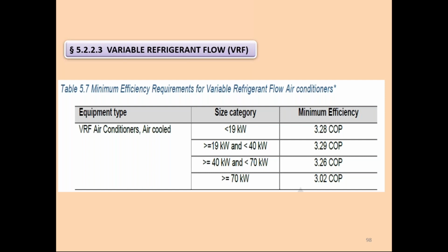And also part load performance of VRV is good. So that means for 10 tons of air conditioning, you will have to install probably 13 or 15 tons of air conditioning VRV system, so that the system will operate at part load and will be efficient. So your first cost of VRV is also very high because you use more gas, you use copper, as well as a little oversized system. But if you have variability in your loading, then still it would pay back.